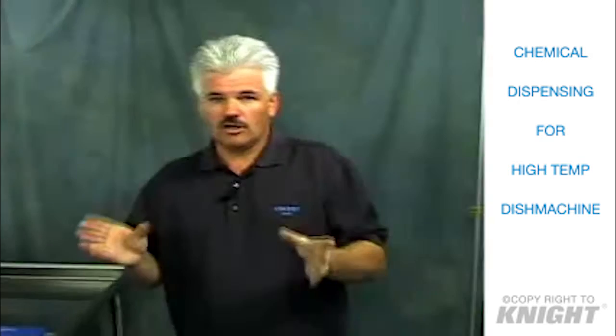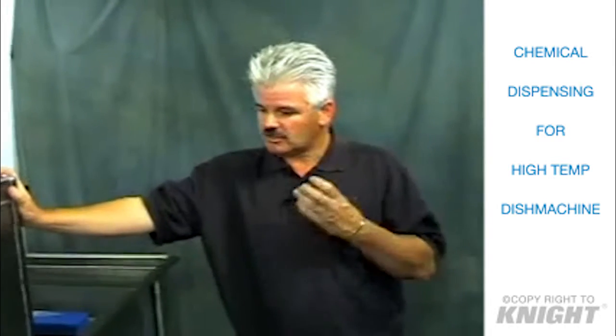Now, a lot of people might ask why you would want to go to a probeless operation, or people that like probeless might ask why you'd go to a probe operation, and both systems have a lot of benefits. Number one, probe is a very effective way of controlling powders or solids because everything is being read, the information is being sent and received back to the dispenser constantly because it's monitoring the level of conductivity or how much alkalinity is in the water.